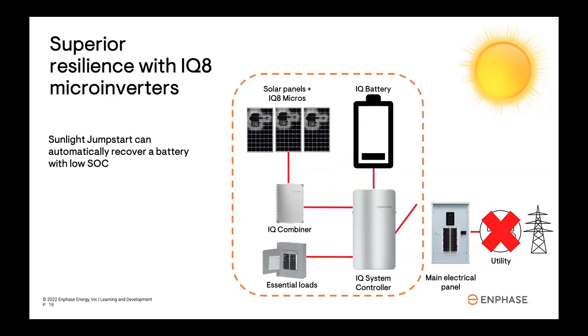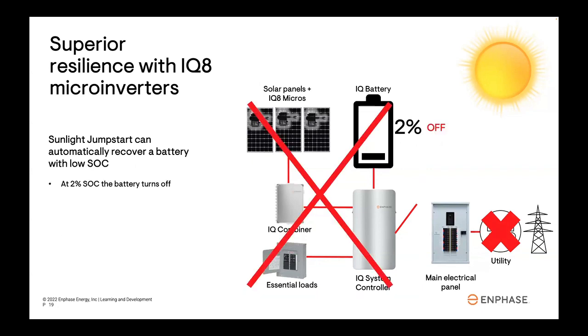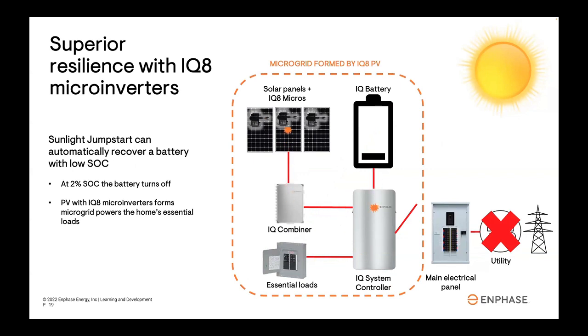Now let's compare that to the Enphase energy system with Sunlight Jumpstart. With Sunlight Jumpstart, if the battery gets down to 2%, the same thing happens initially - it will shut off, just like typical AC coupled systems. However, because the IQ8s on the solar array are grid forming, they can form the microgrid by themselves without support from the battery, as long as there's enough solar power available to power the home's loads. They'll power the home, and all that excess power goes to recharging the battery. Essentially, the system automatically recovers without support from the battery.